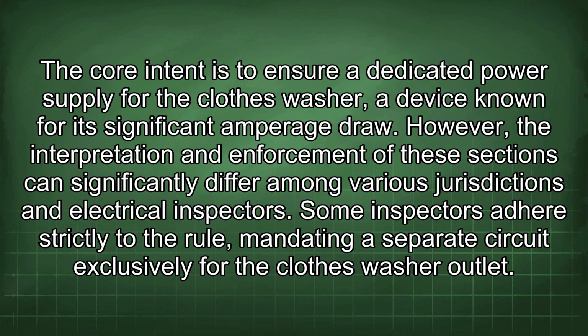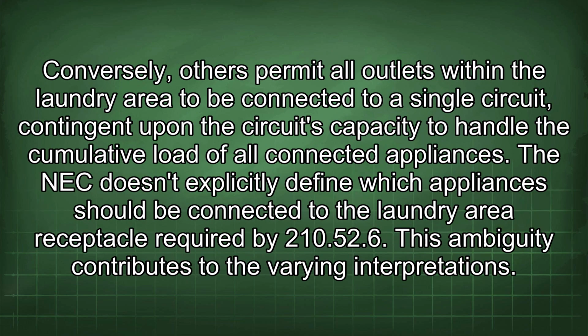Some inspectors adhere strictly to the rule, mandating a separate circuit exclusively for the clothes washer outlet. Conversely, others permit all outlets within the laundry area to be connected to a single circuit, contingent upon the circuit's capacity to handle the cumulative load of all connected appliances. The NEC doesn't explicitly define which appliances should be connected to the laundry area receptacle required by 210.52(F). This ambiguity contributes to the varying interpretations.